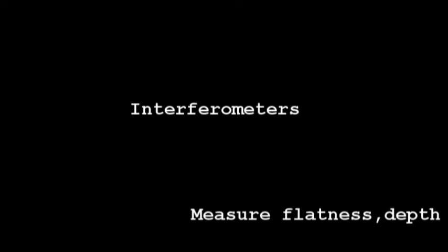Its use overcomes the disadvantages of optical flat by incorporating a refined arrangement. Interferometers are optical instruments which are used for measuring flatness and determining the length of slip gauges. They are based upon the interference principle and employ the wavelength of light as their measuring units.